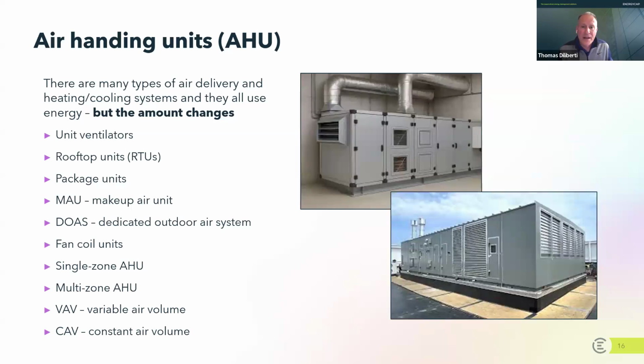The best example I can think of is a kitchen. Many times there's a massive exhaust fan pulling a lot of air out of the kitchen. You might have 1,000 or 2,000 CFM of air being pulled out. These units replace that air with what's called neutral air. So you might have cold outside air that's heated up to a neutral temperature, roughly 68 or 70 degrees, and these systems simply replace the air that was pulled out. So makeup air units and dedicated outdoor air systems are typically used in very specific cases.